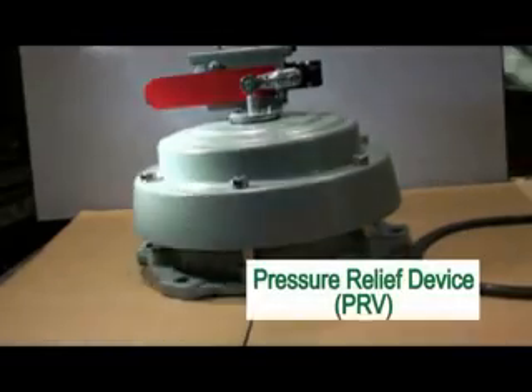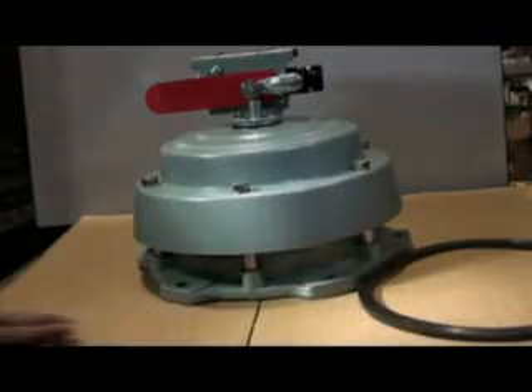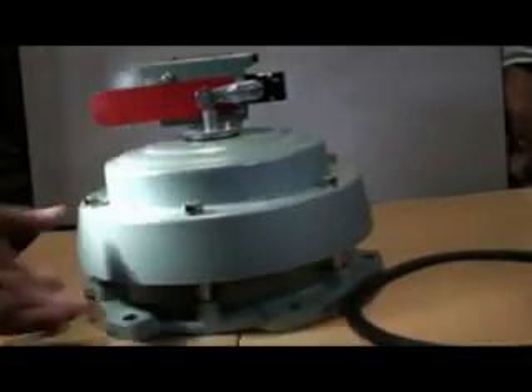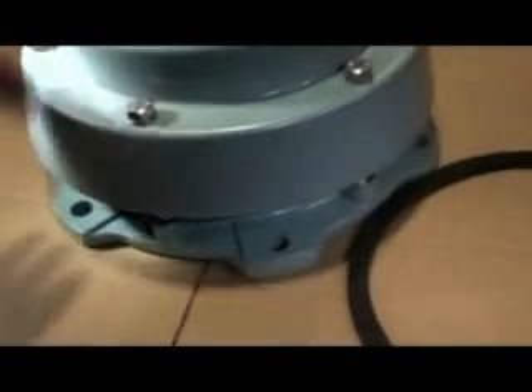Pressure Relief Valve (PRV). This is a 6-inch PRV. When you remove it from the box, you will get a 6-inch mounting ring or gasket. There are 6 mounting holes. When we mount it, the fasteners will be tightened diagonally.